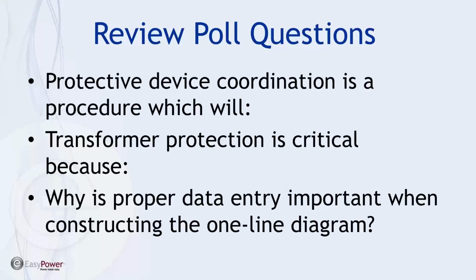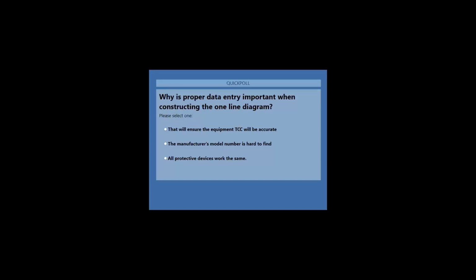But yeah, protective device coordination is critical on transformers because they're expensive and they affect the whole plant. And realistically, you're going to take a long time if you have to replace one. So transformer protection is particularly valuable. And then finally, what is the proper data entry? Why is proper data entry important when constructing a one-line diagram?